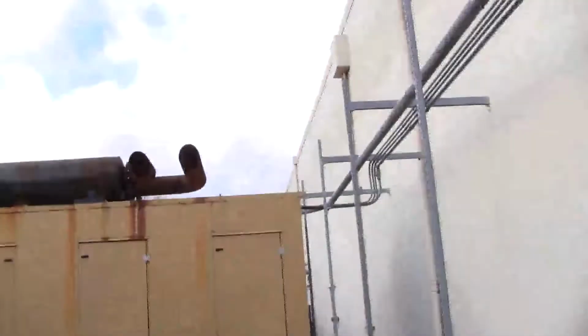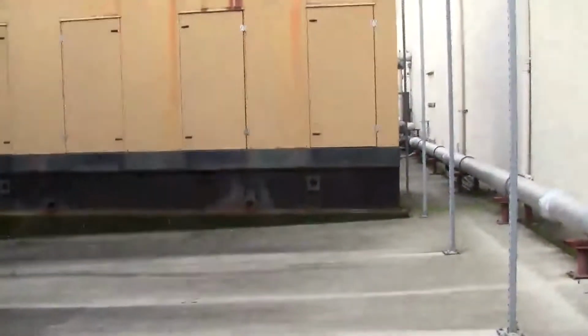Inside this enclosure is a 1,500 gallon day tank, and below it is a 3,500 gallon expandable tank. We have this filled every quarter, and we have an agreement with two fuel providers already set in place where if we start running out of fuel, they will be out within 24 hours. So with 3,500 gallons and the 1,500 gallon tank, we can run for around 4 days, and by then the fuel provider had better be out.